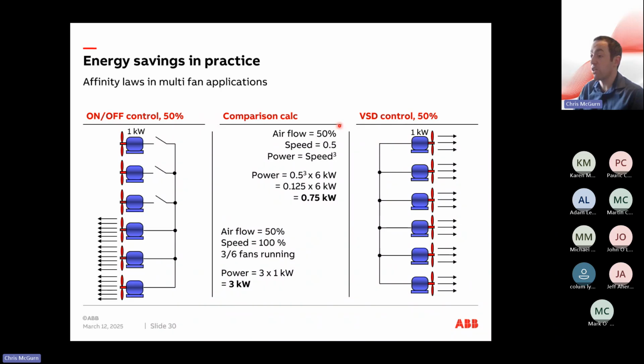So using the calculation that we did earlier, you can see that with VSD control, and assuming a 1 kilowatt load across each of the fans, the actual power being used on the VSD controlled fan array is 0.75 kilowatt, whereas with on-off control, the power being used is actually 3 kilowatt. So there are significant savings to be had when you consider what you actually need compared to what you actually have on site. This is why we really focus on VSD control for these types of applications.